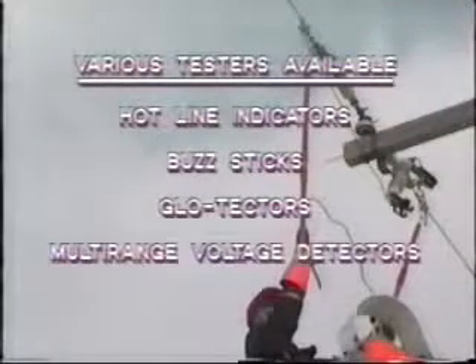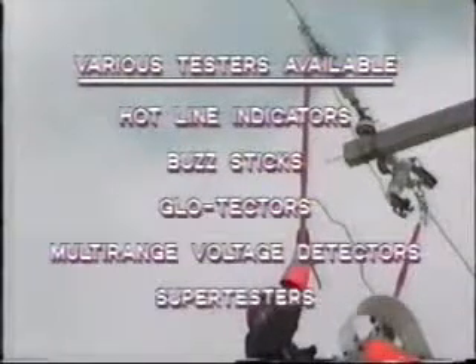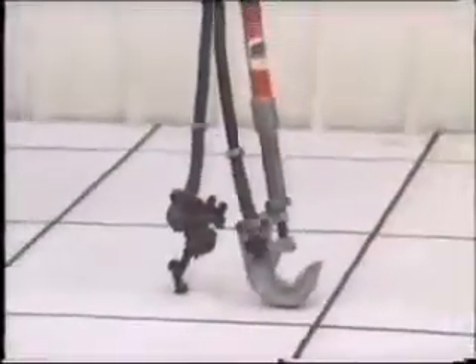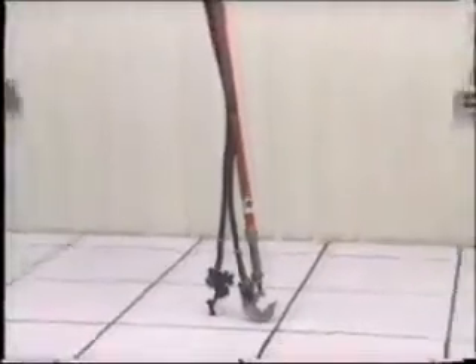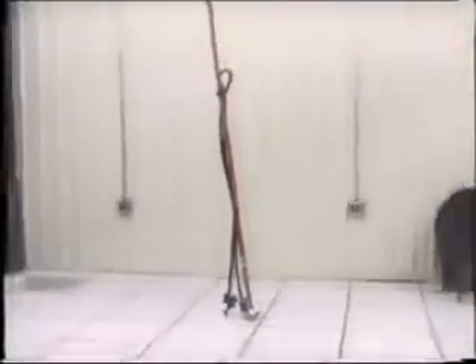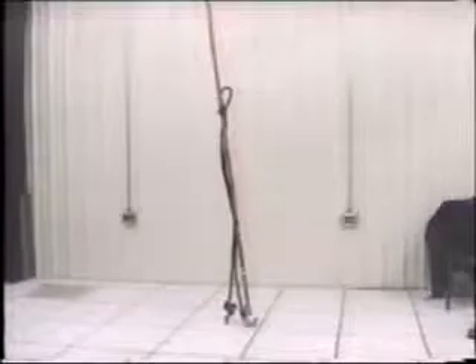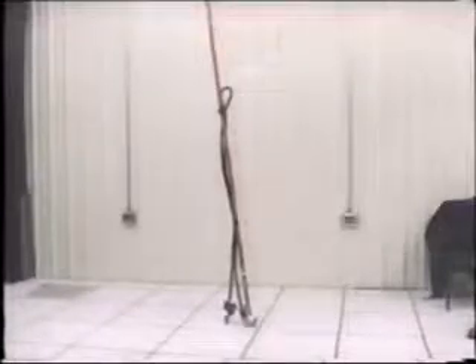Various approved testers are available for different voltage levels, such as hot line indicators, buzz sticks, Glo-tectors, multi-range voltage detectors, super testers. Always prove the tester on a live circuit before checking that your circuit is actually dead. When grounding equipment, remember to attach your grounding cable to the ground first, and then to the equipment. Generally, several grounds are attached. Remember to work between these grounds.